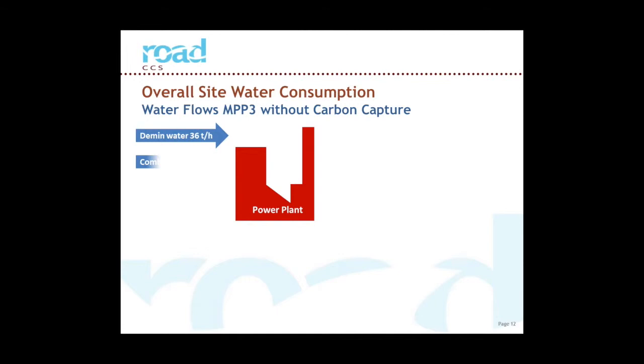We've got water coming in effectively in the coal. Some of it's moisture in the coal, some of it is water that's formed during combustion because there's hydrogen in the coal, and when you burn it, that forms water, forms steam. So in terms of the water balance, that's quite an important feature, that there's 155 tonnes an hour coming in from the fuel and the combustion process. A small amount of rainwater. The fresh water I've mentioned, this is used in the FGD to quench the flue gas. Brings the flue gas down from above 100 degrees down to 50. And there's a small amount of drinking water. And then the main water usage, which is the seawater cooling, and this is direct cooled.